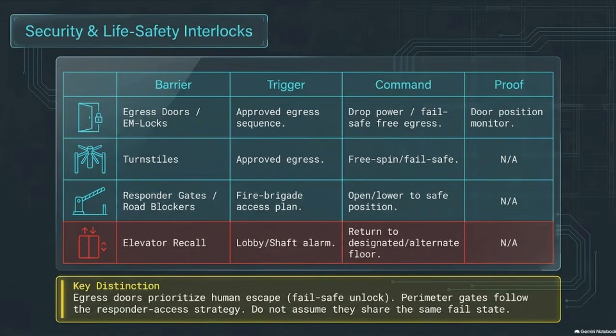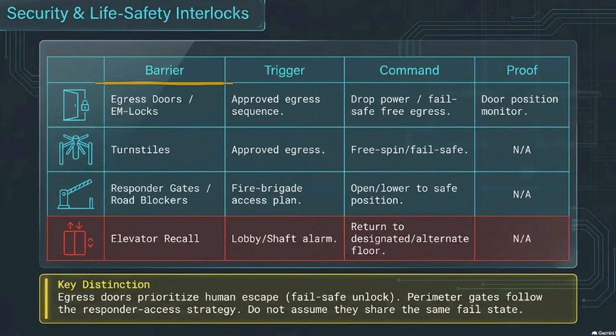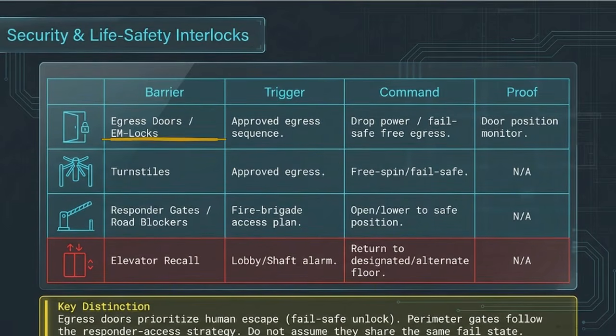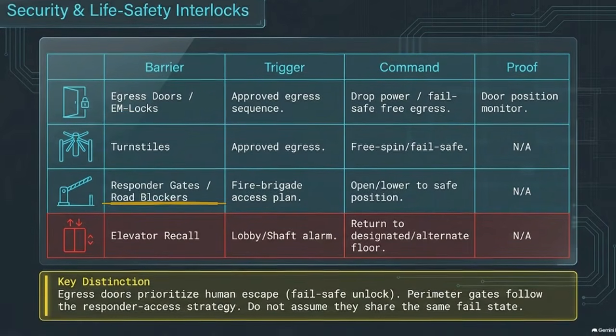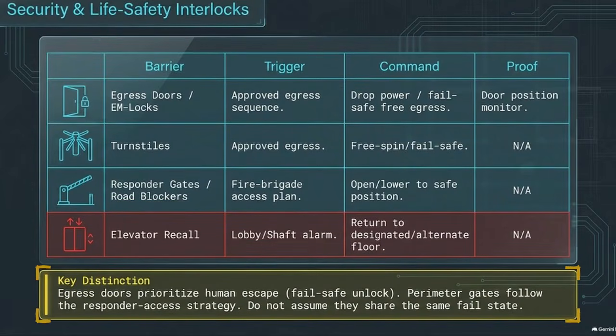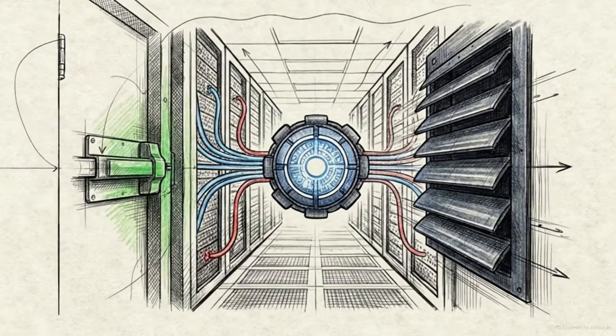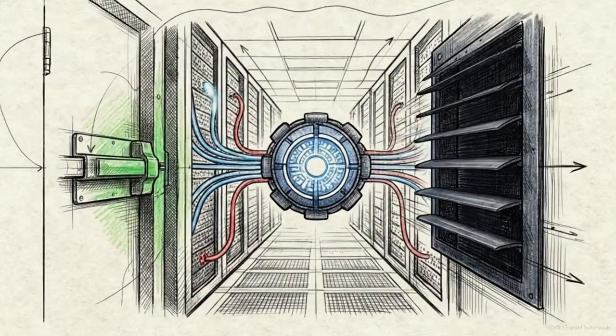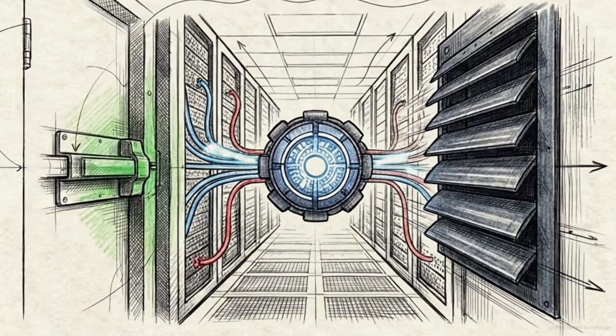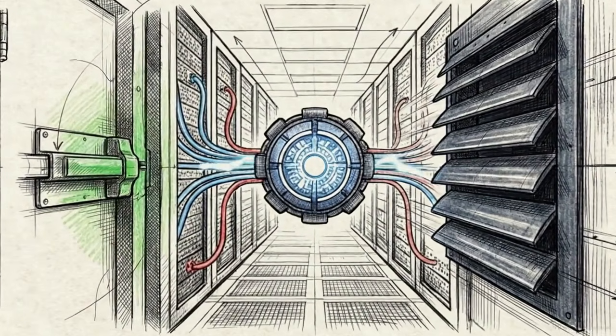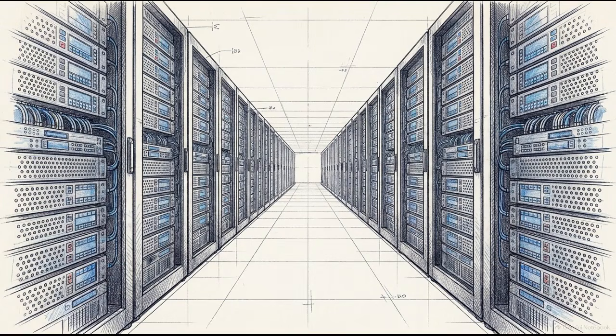This interlocks table shows how the matrix simultaneously commands security barriers. Different barriers require entirely different fail states based on their function. Egress doors and electromagnetic locks prioritize human escape, dropping power for a fail-safe free egress. Perimeter responder gates, however, follow a separate fire brigade access plan. They do not share the same fail state, and the matrix must command them independently. The matrix is a master orchestrator. It executes a complex balancing act, prioritizing the immediate demands of human escape while executing targeted commands to ensure the survival of the surrounding critical infrastructure.